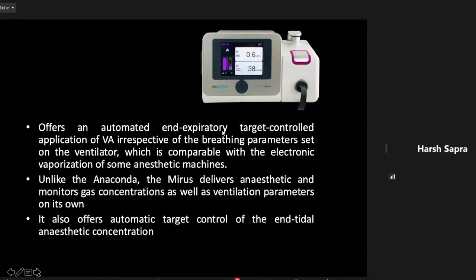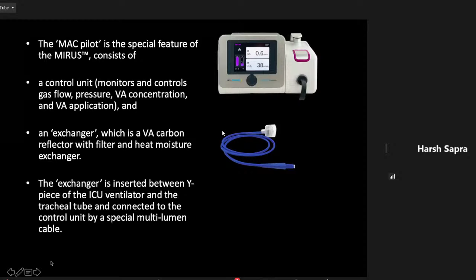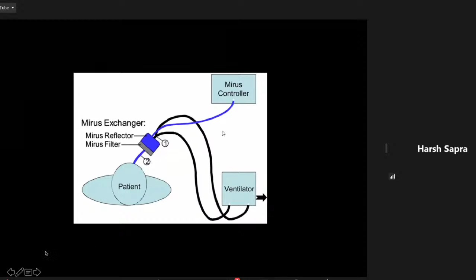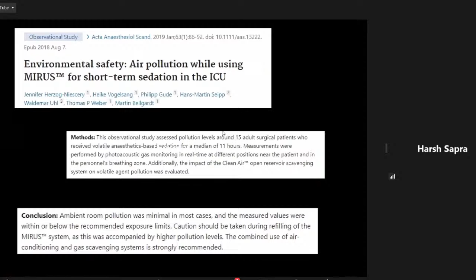An exchanger, which is a volatile anesthetic carbon reflector, is inserted between the Y piece of the ICU ventilator and the tracheal tube, and connected to the control unit by a special multi-lumen cable, which is connected at one end to the Mirus control unit and at the other end to the exchanger. So this is the Mirus exchanger, Mirus reflector, and the Mirus filter. It goes on to the Mirus controller, and obviously this goes on to the ventilator. For environmental safety, ambient room pollution was minimal in most cases, and the measured values were within or below the recommended exposure limits. The only caution given was while filling the Mirus system.